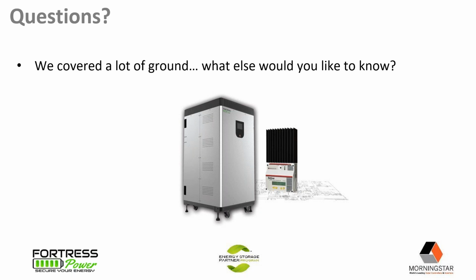That's a really great question. I have a two-part answer. I like to recommend that for sizing batteries, you want your battery to be double the size of the solar array as a start. Sizing batteries is easy but complicated, because while you have that rule of thumb, it depends on what application you're sizing it for. If you're sizing for backup or self-supply, you want to make sure it's sized well enough that the person isn't stuck when they need the battery because it's undersized. At the same time, when sizing your critical load panel, you don't want to oversize it, because if the inverter and battery turn on, it might shut down the whole energy storage system if that load panel is oversized.